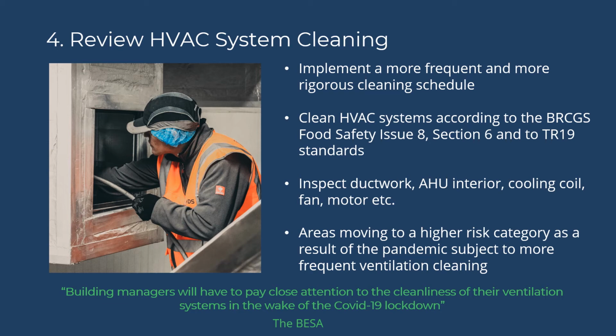Cutting back on cleaning could increase the risk of fire associated with the buildup of dust, debris, and particularly grease in ductwork and fryer extract flues. The BESA indicates that grease buildup should be kept below 200 microns.